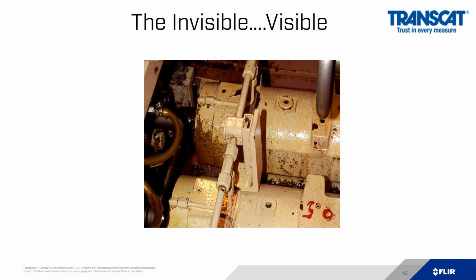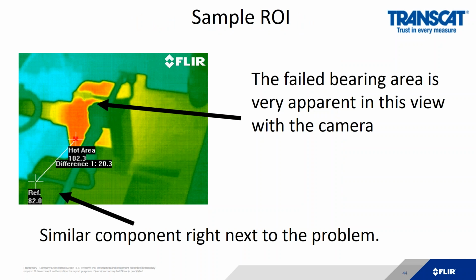So here's a classic example. The invisible. We make the invisible visible at FLIR. So I have these two motors, these two spindles right here. With our eyes, we can't see any difference. Maybe one appears to be a little dirtier than the other. But under infrared, we see the one is much warmer than the others by roughly 20 degrees. They're doing the same amount of work. They should be the same exact temperature. But we discovered that the one on the top has about a 20-degree difference.